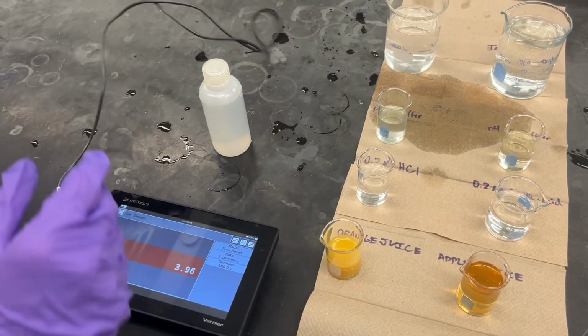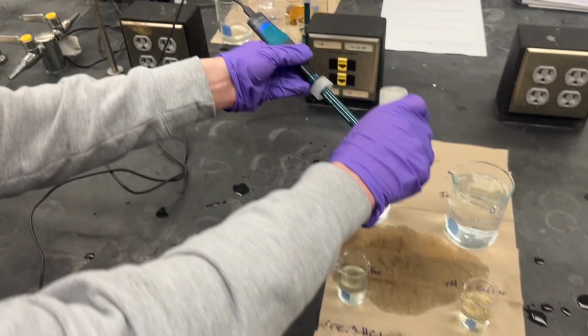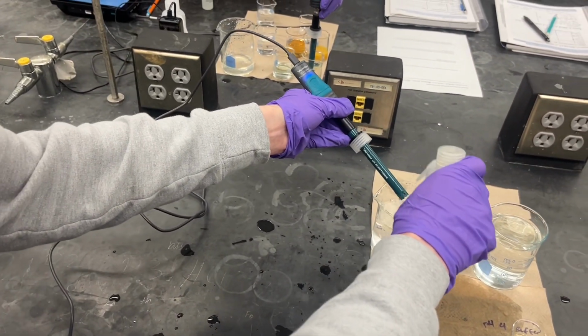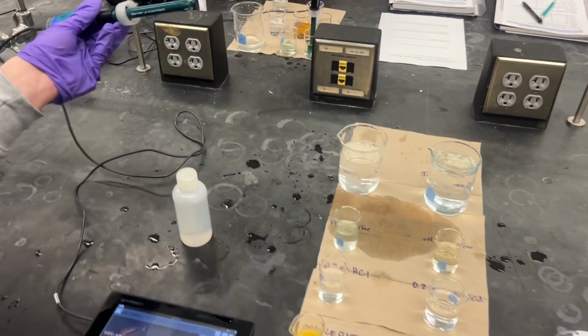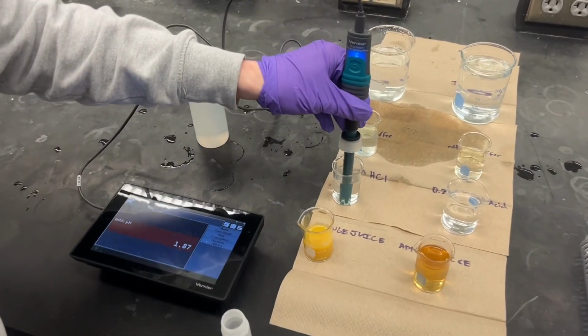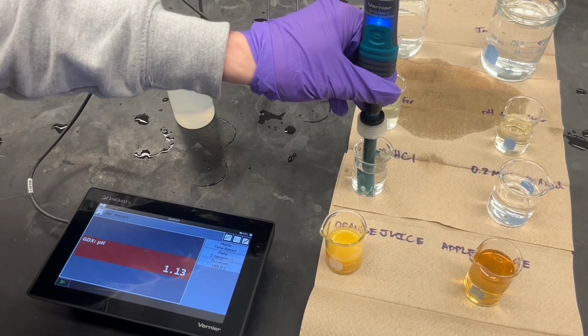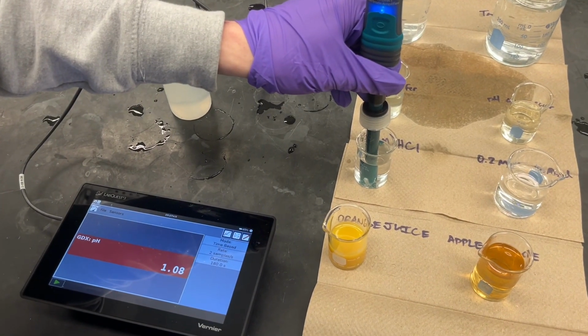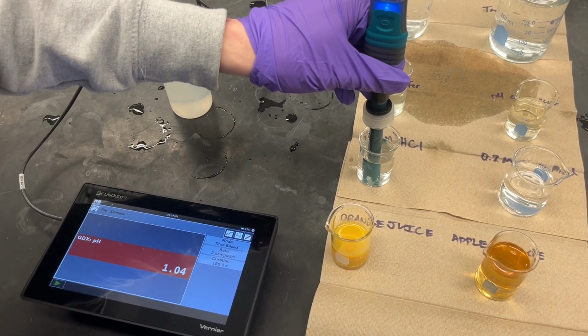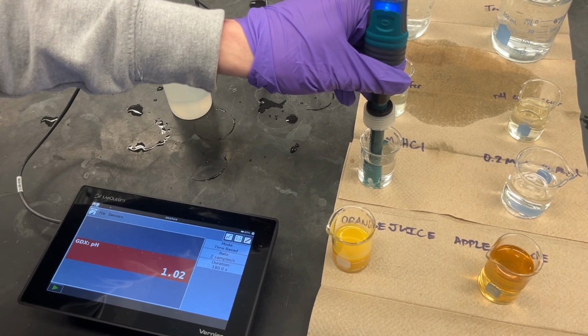By calibrating the meter using this 2-point calibration method, it makes the probe able to read the pH value of many different solutions. We then use the calibrated pH probe to find the pH of a 0.2 molar solution of hydrochloric acid. After that, we use the calibrated probe to find the pH of known and unknown solutions.